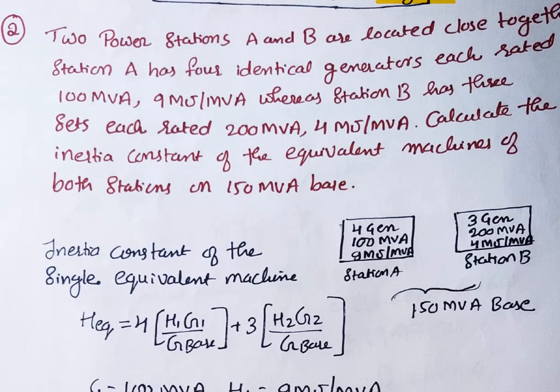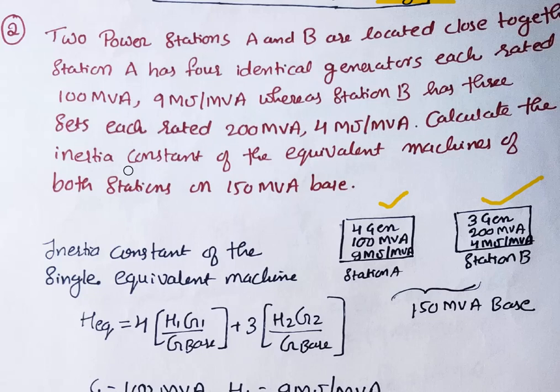The second question is simpler. Two power stations A and B are located close together. Station A has 4 identical generators, each rated 100 MVA with H = 9 megajoules per MVA. Station B has 3 generators, each rated 200 MVA with H = 4 megajoules per MVA. Calculate the inertia constant of the equivalent machine on a base of 150 MVA.